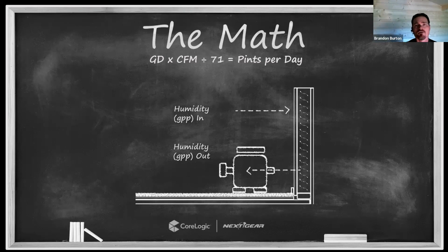So how do we monitor an inter-air drying system? How do we know that an inter-air drying system is effective? In simple terms, we monitor an inter-air drying system the same way that we do a dehumidifier, just in reverse. We monitor a dehumidifier by measuring the air going into it, determining the grains per pound or humidity ratio. Then we monitor the air coming out of the dehumidifier in grains per pound or humidity ratio. The difference between those two tells us how much water the dehumidifier has removed, right? Grain depression. With an inter-air drying system, we're doing the opposite.